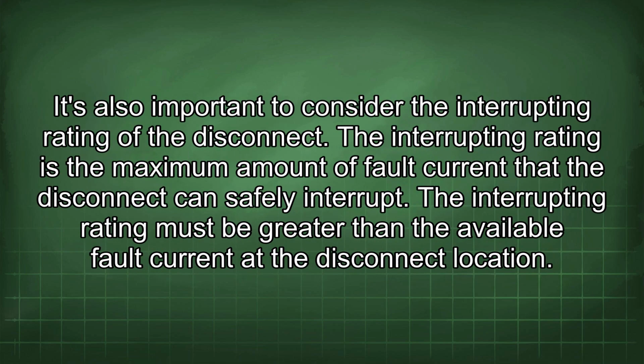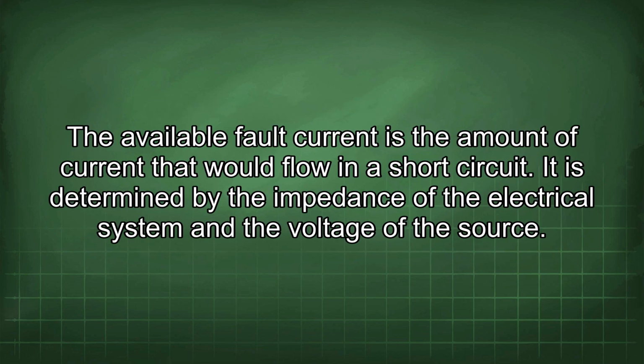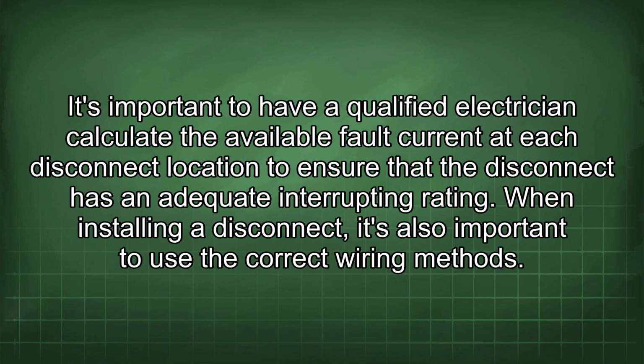It's also important to consider the interrupting rating of the disconnect. The interrupting rating is the maximum amount of fault current that the disconnect can safely interrupt. The interrupting rating must be greater than the available fault current at the disconnect location. The available fault current is the amount of current that would flow in a short circuit. It is determined by the impedance of the electrical system and the voltage of the source. It's important to have a qualified electrician calculate the available fault current at each disconnect location to ensure that the disconnect has an adequate interrupting rating.